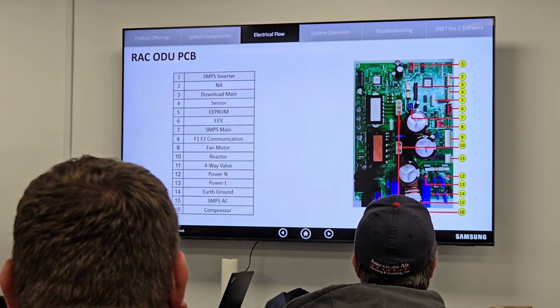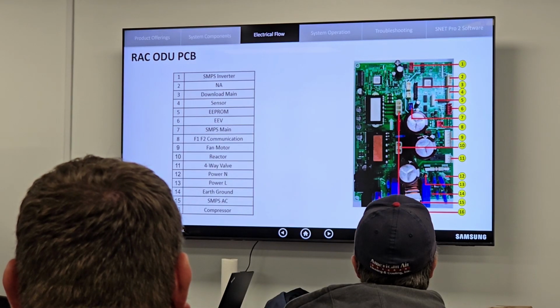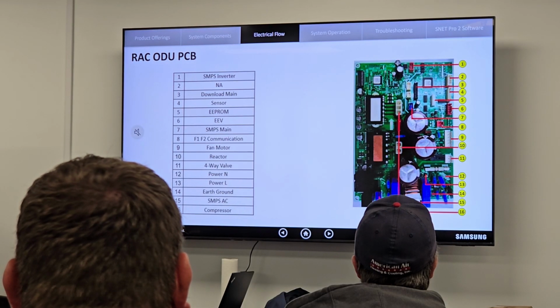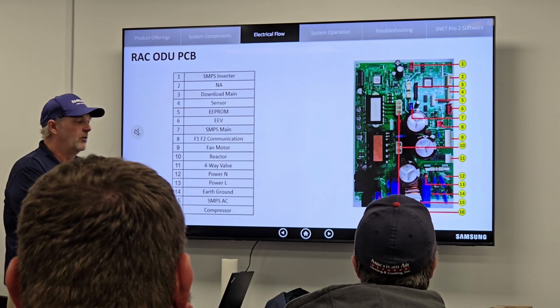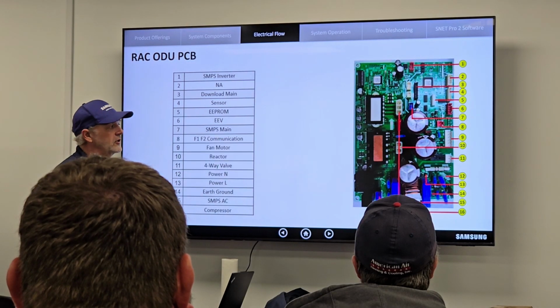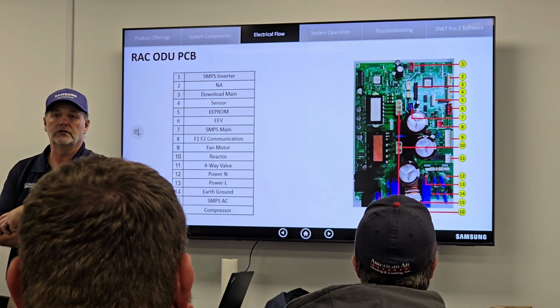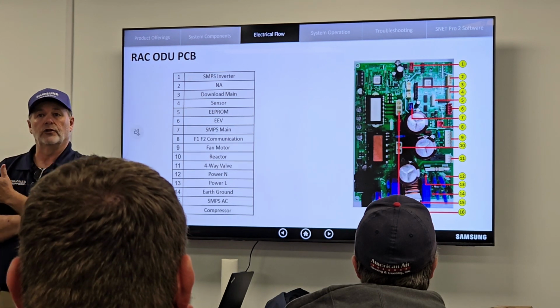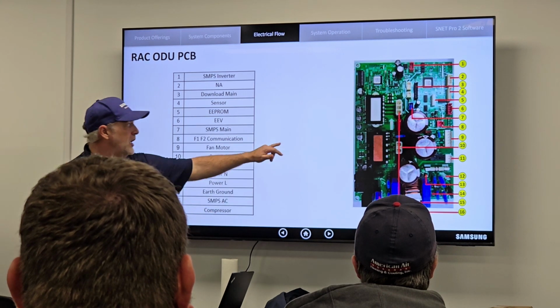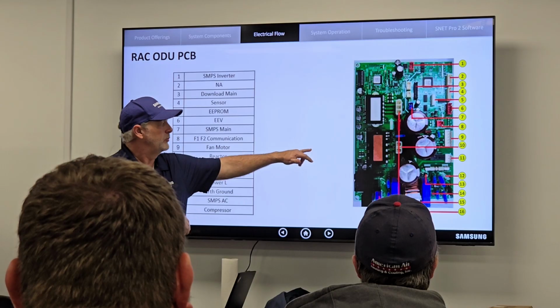Those are my IGBTs. My IGBTs produce a lot of heat, so what do they connect to? The heat sink. The heat sink is nothing more than an aluminum block. That's all it is. But between the aluminum block and this inverter control board, we have to have grease, a dielectric grease. The reason is because these are not, how can I put it, true.